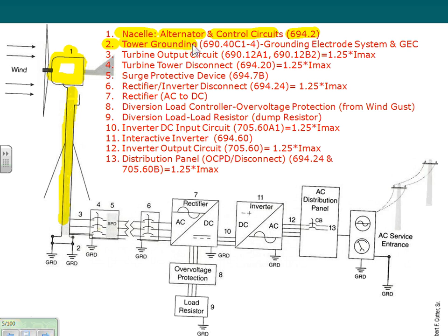for now we're talking electricians: grounding and bonding. The most important thing when it comes to the tower is the grounding and bonding. So the code, and I laid out where the code says that, requires you to create a grounding electrode system. Long story short, you have to drive a ground rod in the ground and tie a copper wire, number 6 minimum, to that ground rod and tie it to the base of the tower. That's a must-have by the code. So if you're installing this system, the first thing you're going to do as you erect this tower is have a ground rod.